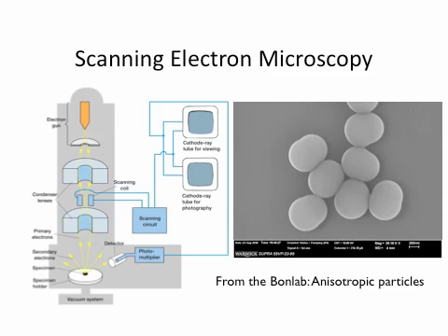So what about more expensive toys? I would say not more advanced, more expensive. One of the toys is scanning electron microscopy. Now, you may have seen this already or not, so there are some pictures later of this particular equipment. But basically what you do is you image with an electron gun, and there are a few lenses here that make sure you can get your image sharp. And typically the resolution of a field emission SEM on a good day takes you down to about 10 nanometers, I would say. So smaller objects you won't be able to see.